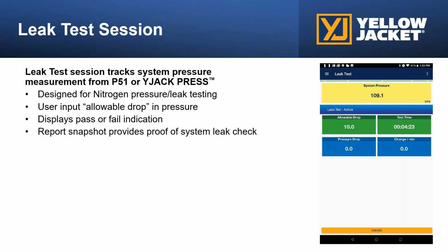If there's any pressure drop greater than the allowable drop or allowable change, then it will let the contractor know that in real time. Usually, if it does let the contractor know that there is an issue, it'll happen in the first 30 seconds to 2 minutes, because usually there's a leak somewhere in that line set, right? The contractor goes back, they would fix whatever the issue is, fix that leak, start the leak test again. Once it passes, that contractor knows that they installed the system correctly.